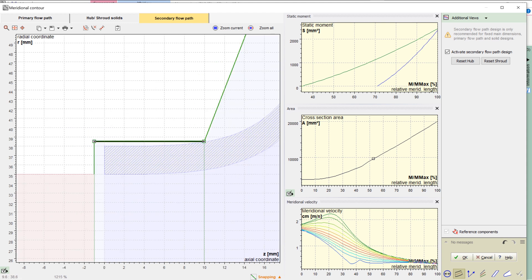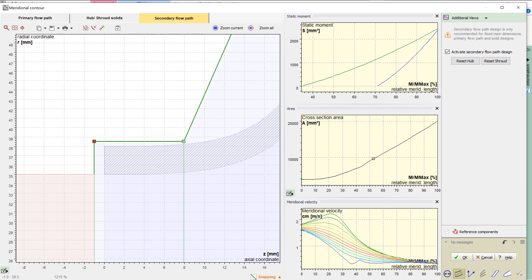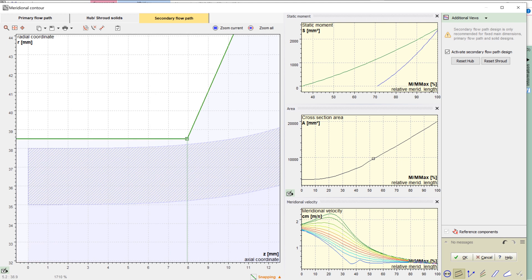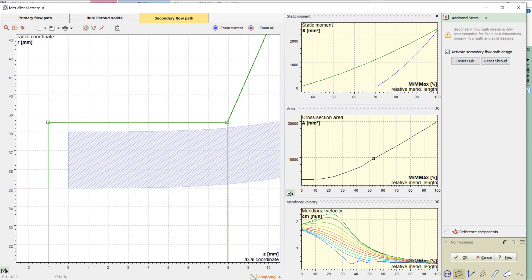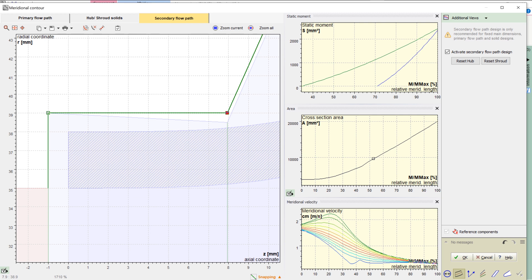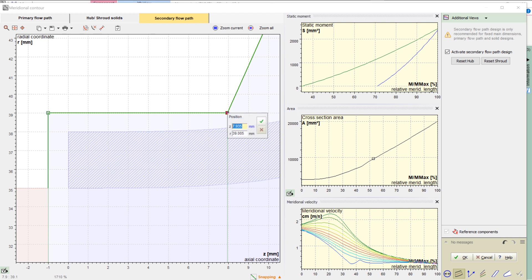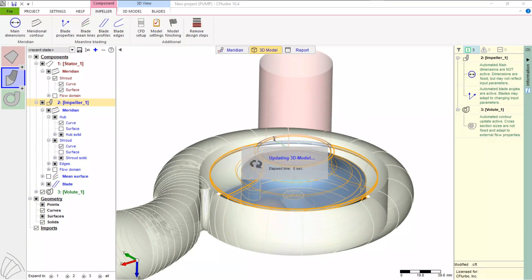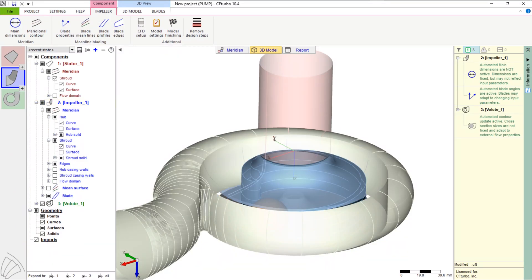The corner points can be adjusted graphically or numerically. All lines can be transformed into Bezier splines. For example, here we modify the casing contour near the eye of the impeller. This is very often used to design a small gap to minimize volumetric losses. In general, the shroud contour of the impeller can be adjusted accordingly. For example, the user can model a wear ring or a simplified labyrinth seal to prepare the CFD geometry in CF Turbo.